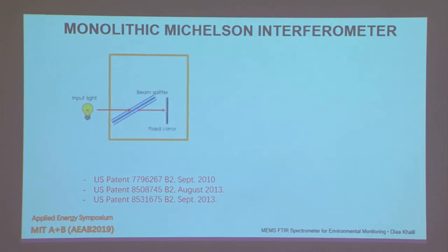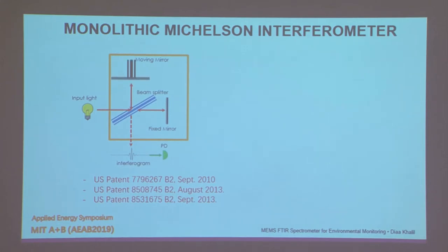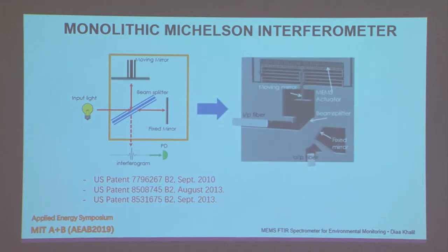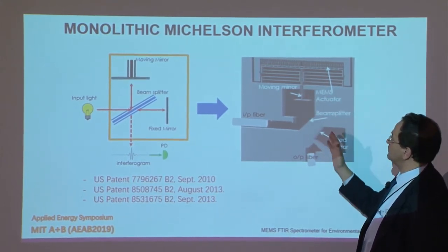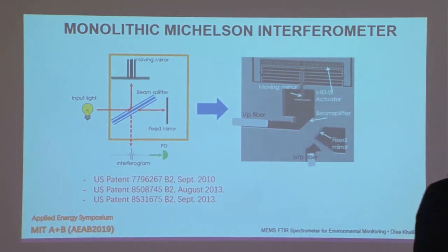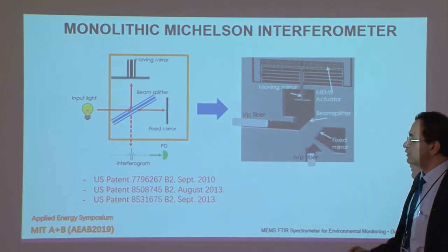The idea is quite simple: an FTIR spectrometer is simply a beam splitter with two mirrors — one moving mirror and one fixed mirror. Mixing the two signals back from the fixed and moving mirrors, you get an autocorrelation function. When you do the Fourier transform of this autocorrelation function, you get the spectrum. You can build this on a MEMS substrate simply by having the silicon interface itself act as the beam splitter, with a moving mirror connected to a comb-drive actuator, which is now classical in MEMS.